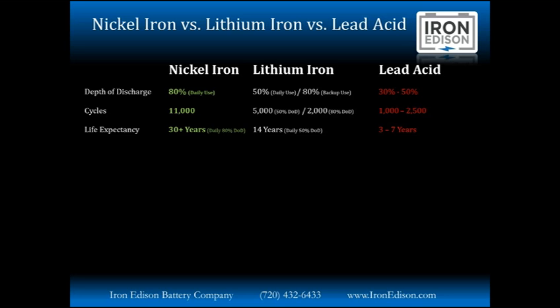If you're using a lithium battery as a battery backup application where it's not going to be cycled on a daily basis, but maybe weekly, monthly, a couple times a year, we recommend doing an 80% depth of discharge on the design when you size the battery. By doing that, you will get a shorter life, 2,000 cycles, but because you're not going to be cycling it on a daily basis, you're still going to get many years of life out of that lithium iron battery in a battery backup situation. Now, of course, compare these numbers to the typical lead acid battery. You can only do 30 to 50% depth of discharge with a lead acid battery, depending on manufacturer, and you'll get 1,000 to 2,500 cycles. Expected life, 3 years, 5 years typically. Best case scenario, maybe 7 years of life out of a lead acid battery.